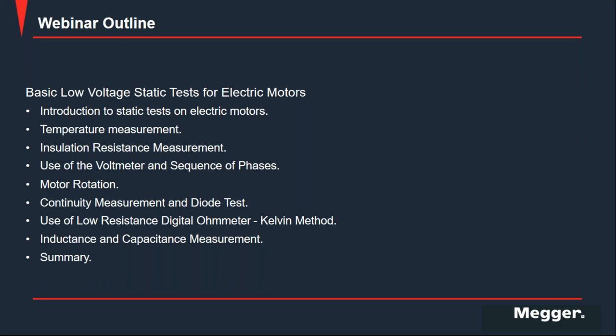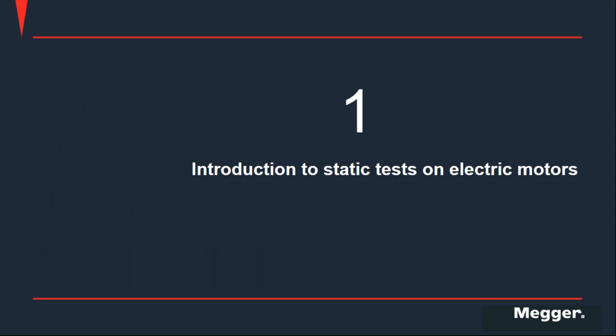First of all, we'll define the static test, and then we'll see seven static tests that allow us to verify the condition of the motor insulation system. We're going to talk about temperature measurement and how this variable affects the insulation system test. Also, we're going to see why we have to use the voltmeter and verify the phase sequence, and how that verification helps us to know the motor rotation. Then we'll talk a little bit about the continuity and diode test, and finish with the Kelvin method and the inductance and capacitance readings. At the end, we'll check bullet points that summarize the importance of these tests. All right, let's begin.